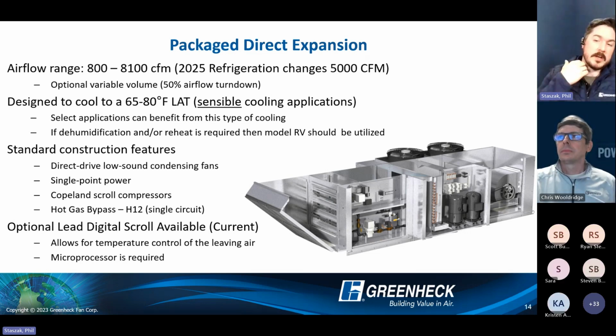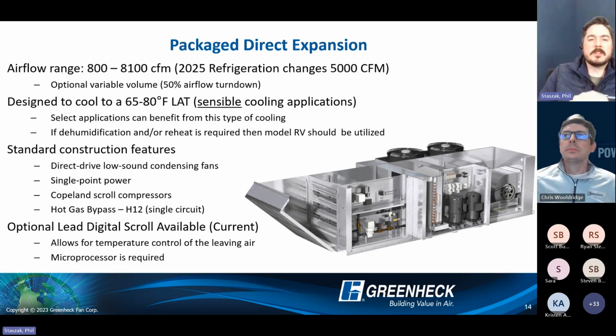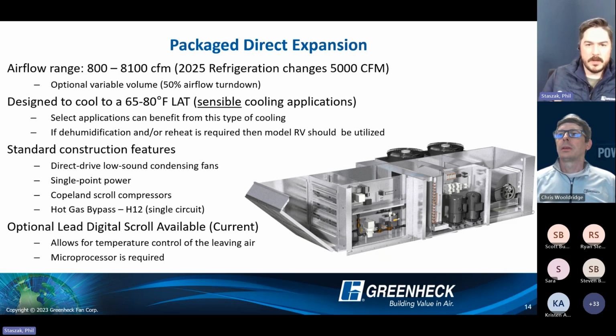Currently, the PDX or the condensing section hangs off the backside of our unit. We're actually looking at an engineered design, more of a V-bank module on the top of the unit now, so the units will get a little bit taller. So just interesting changes to talk about right now and discuss going forward for 2025. Current state right now is 8100 CFM, but again, 5,000 CFM is probably going to be the top end of this when we come closer to that 2025 date.